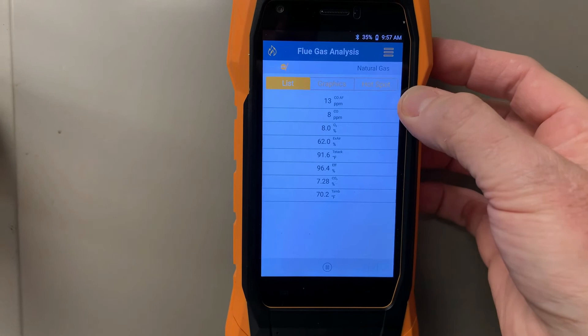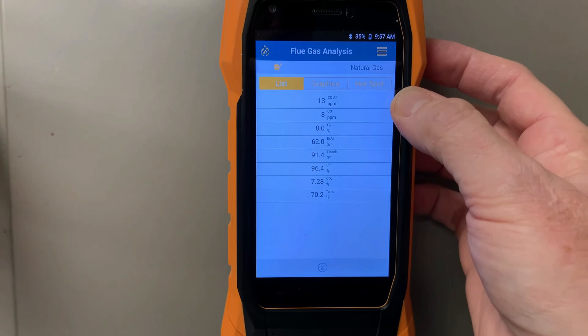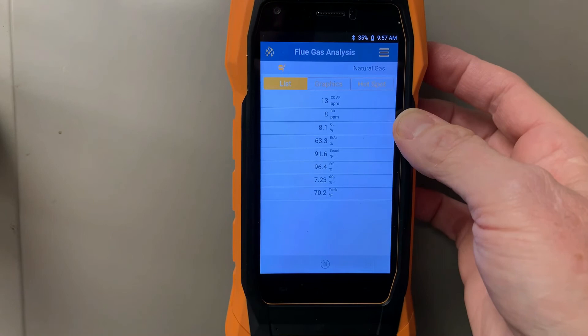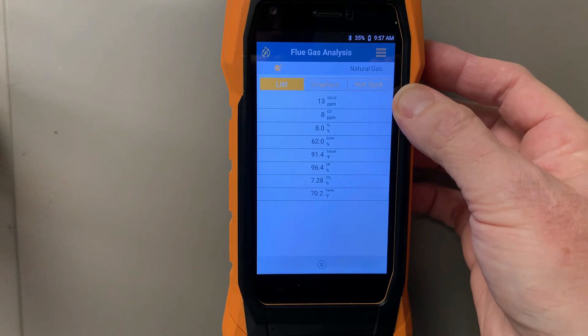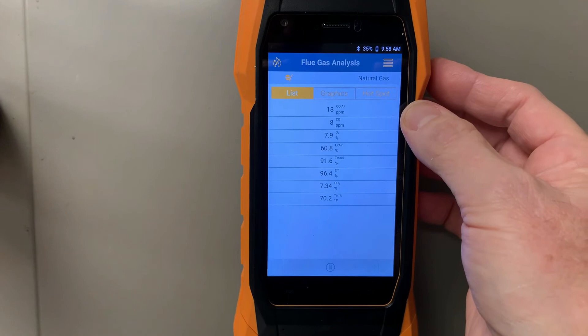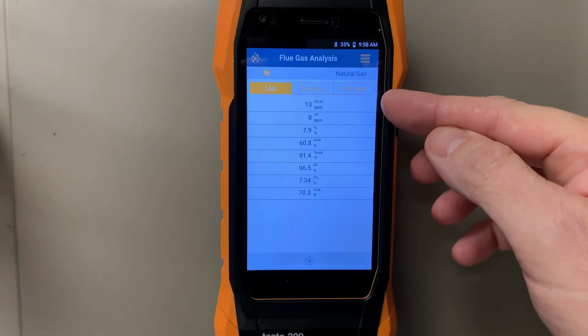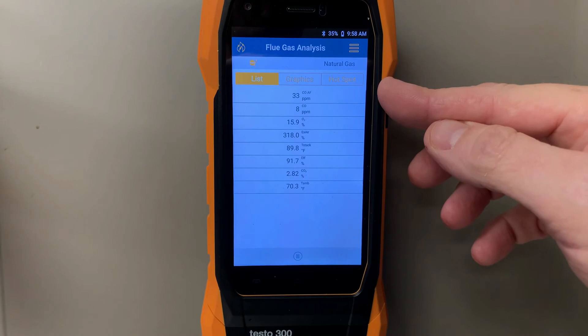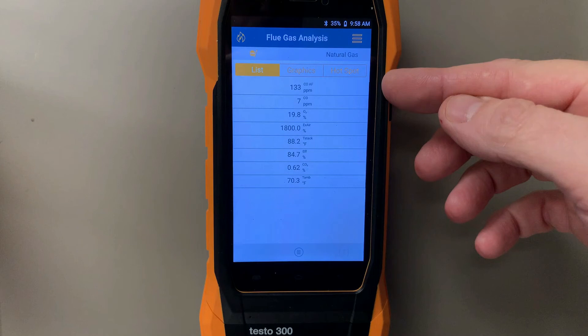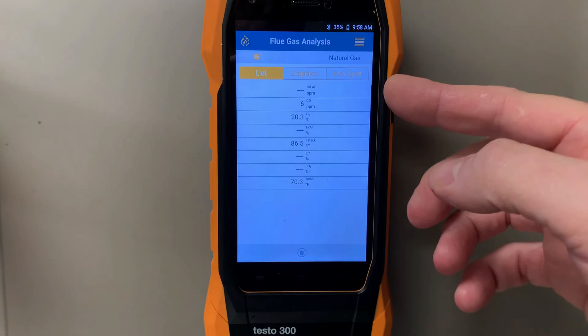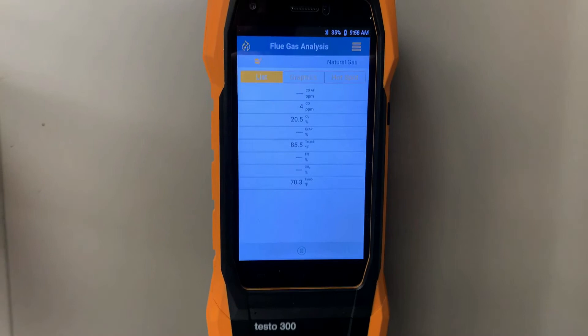Stack temperatures and everything looks pretty good. Right now we are running really consistent — 13, 14, 15 ppm CO air free, and about 8% O2. Those are good numbers. I'm going to shut this thing down now and we're going to watch how high the CO air free goes up on shutdown. Sometimes you can get numbers that shoot up into the thousands — that kind of tells you the valve is leaking fuel when you see something like that.